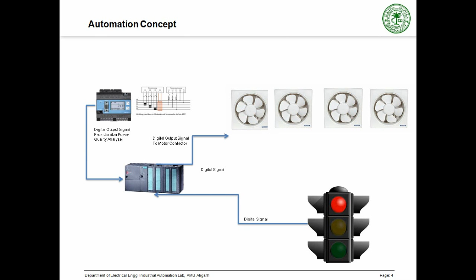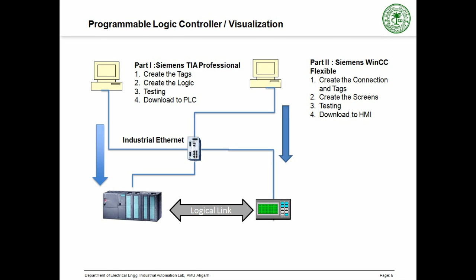System engineering. It has two parts. The first part is for the PLC, containing creating tags, creating logic, and downloading the program to the PLC. The second part contains creating a connection between HMI and PLC, creating a screen, testing, and downloading the HMI screen to the HMI hardware. We have used Totally Integrated Automation software. Here we select PLC S7-300, CPU 314C-2 PN/DP.